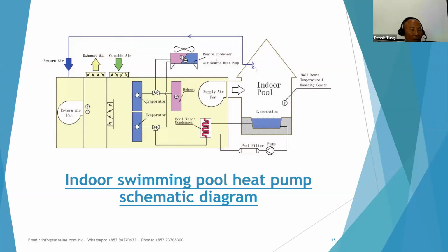So energy is used. On the other side, due to the evaporation of the pool water, the water is cooled down. The temperature drops and people will not feel comfortable, so energy is needed to maintain the pool water temperature. The dehumidification process by the air conditioning system will generate heat, and this heat is used to maintain the pool water temperature. This is a complete recycling of heat energy within this system, with no need to put in additional heaters to heat up the pool water or the air for comfort. So this is a very good example because air conditioning, cooling, and pool water heating occur at the same time.